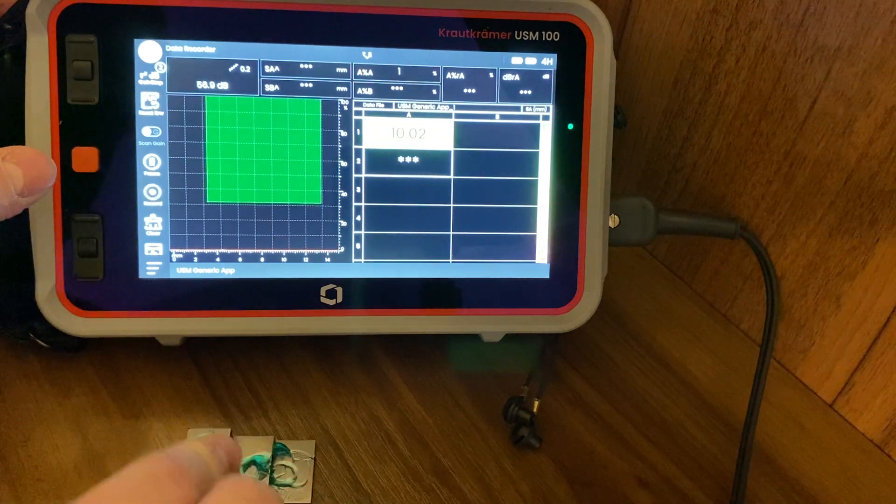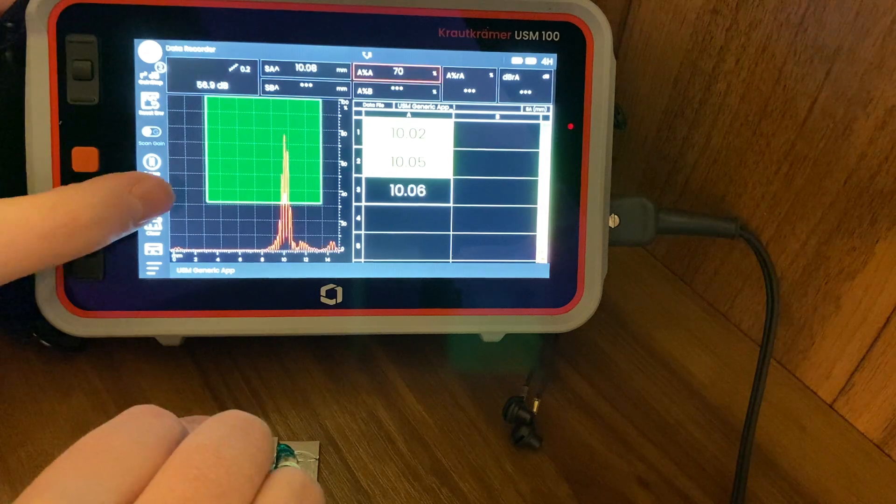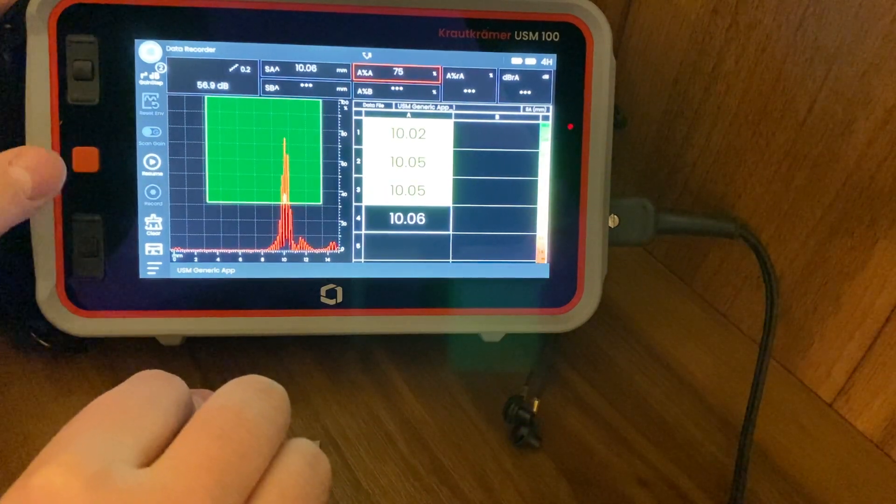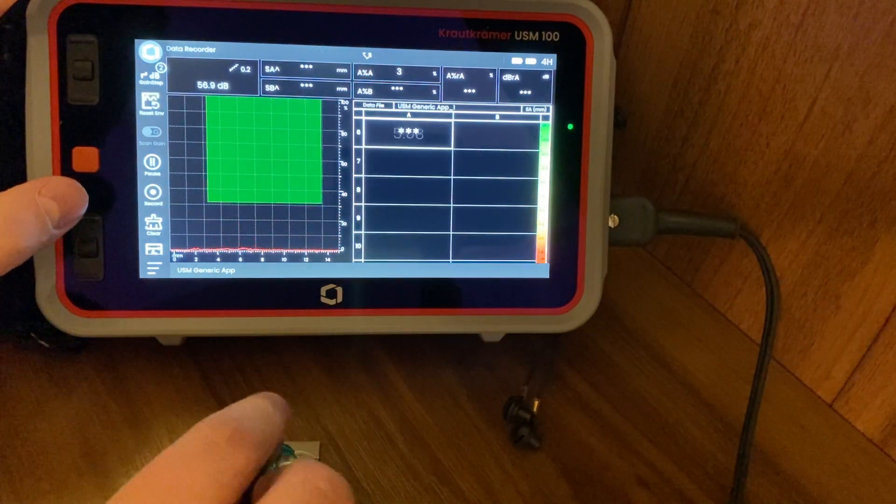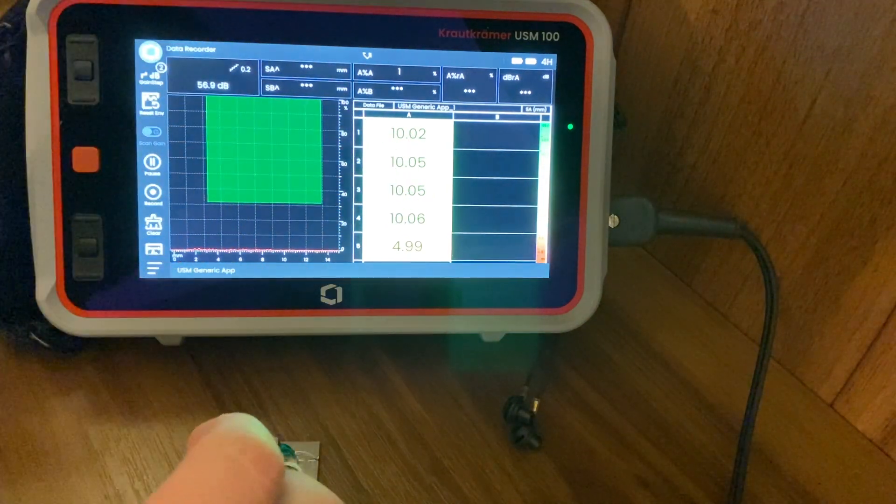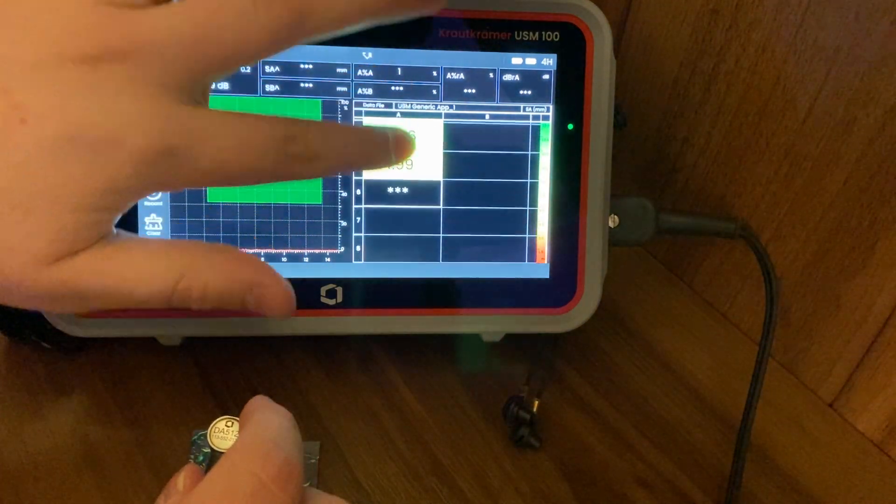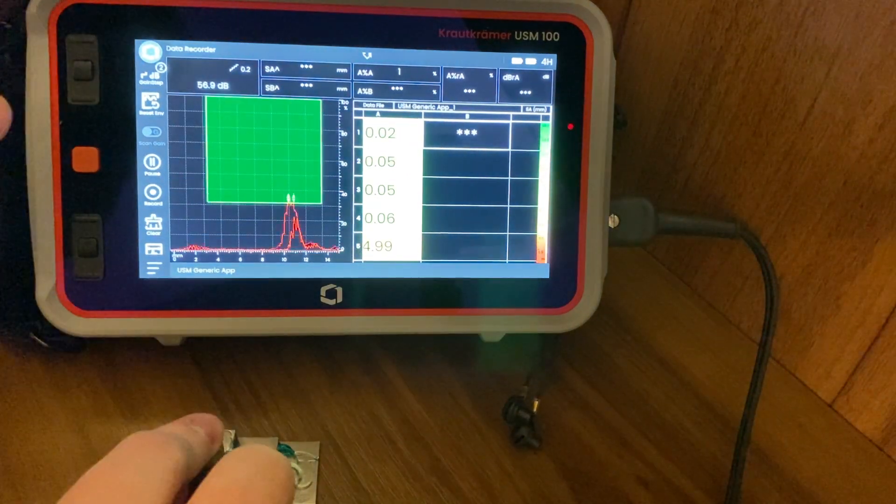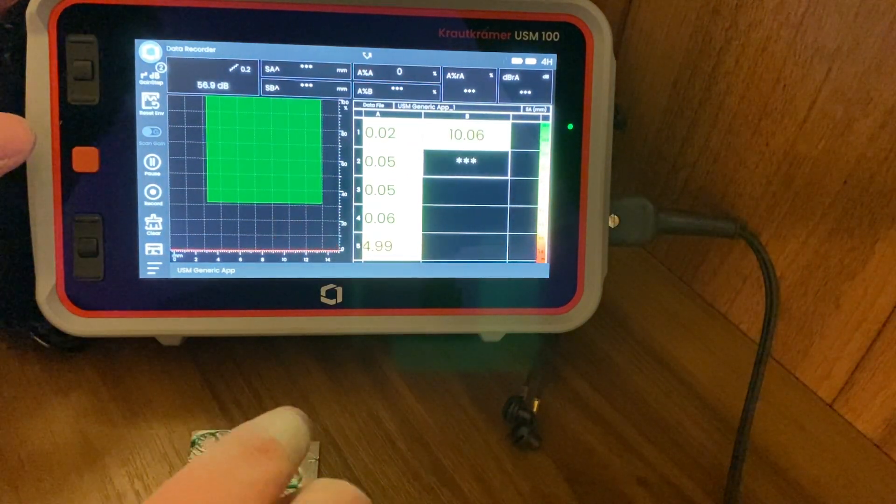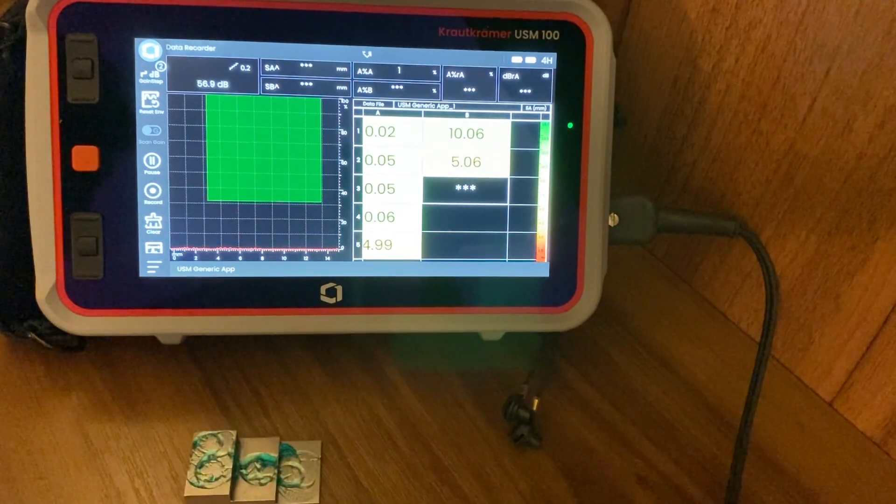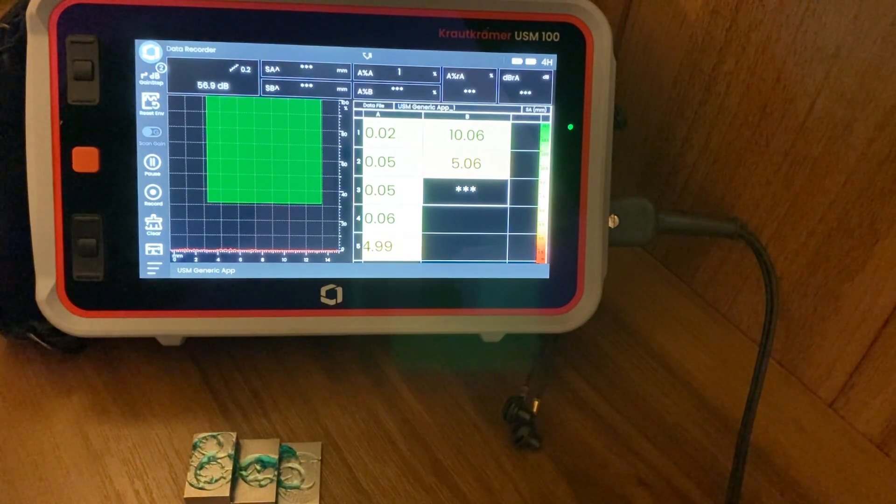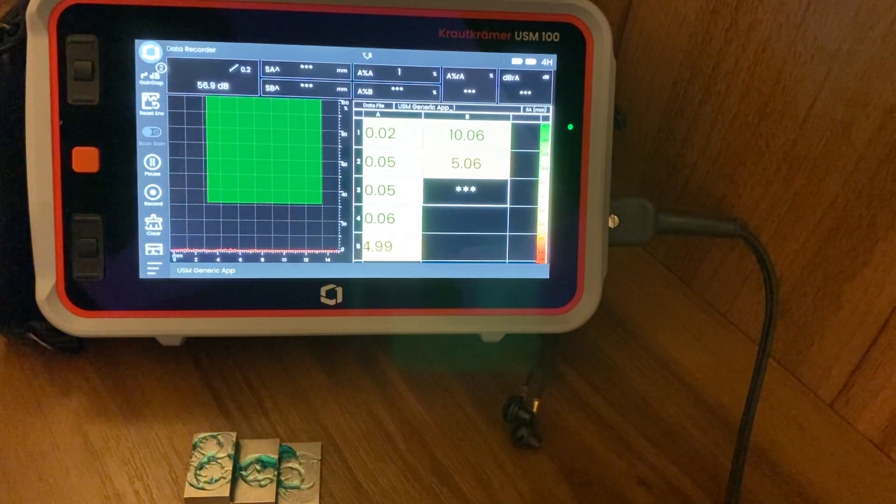If you're doing that point, you consistently go along, hit record. I'm just doing this really quick, I'm not really too worried about how I'm coupled up here. Let's say for example, let's get a 5.1 in there as well. What you're seeing here now is the data points have been recorded. Let's say I finished that one, and then we'll go over to the next section. You start to record data here as well, and basically you move along recording data - very, very simple little tool. It takes the effort of having to hand-write down every reading, which historically we've seen people doing and even with people with newer equipment are still doing this. So this is a very handy little feature.